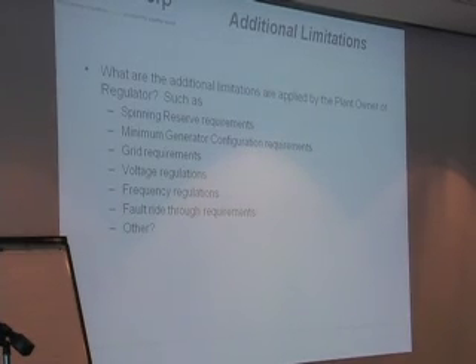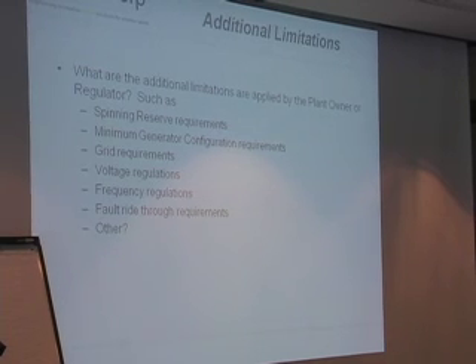Then there are other limitations applied that aren't the fault of the power station. The owner, operator, regulator, or utility may enforce a rule that all power stations must run enough engines to carry the load plus a spare one or two. We've had customers that want two spare engines spinning online just in case two should fail. So how are we ever going to save fuel? We probably don't say that to them. Then you go through the discussion: so your generators are really unreliable then? No, they generally don't fail. Okay, maybe we take one of those off and see some fuel savings? Oh no, that'd be against our internal requirements, and we've worked here for 40 years, so we can't change those.